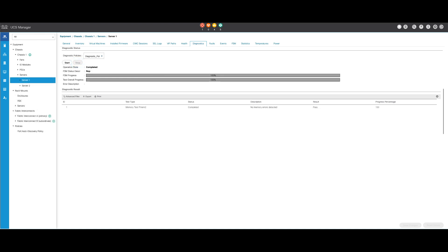You can stop the diagnostic at any time by pressing the Stop button. Once the diagnostic test is complete, the diagnostic result will be displayed. In this test, no memory issues were found. If the result shows Fail, generate the logs for the server and contact TAC for assistance.